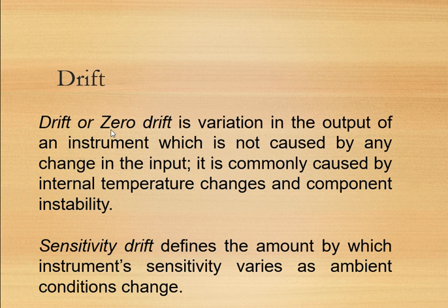Now if you see, there are two to three types of drifts. One is a zero drift, another is a sensitivity drift, and the third is a combination of both. Zero drift is a variation in the output of an instrument which is not caused by any change in the input.